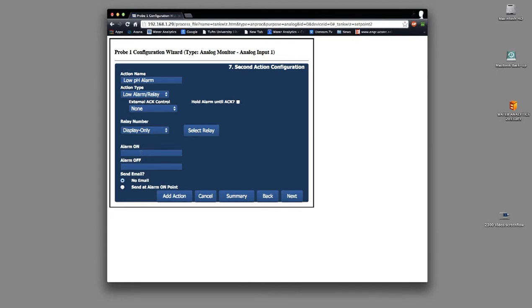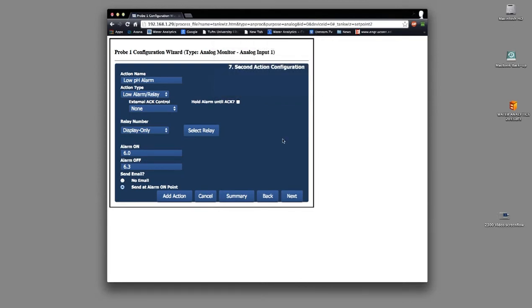I'll choose a pH value of 6.0, below which I do not want my process to go. And since this is a falling process, the reset trip point has to be higher than the trip point. So I'll choose 6.3. This time, I want the 2300 to send me an email message if the process drops below 6.0. So I'll click on the radio button, Send at Alarm on Point. Whoops, looks like we lost communication briefly. Okay, that does happen.